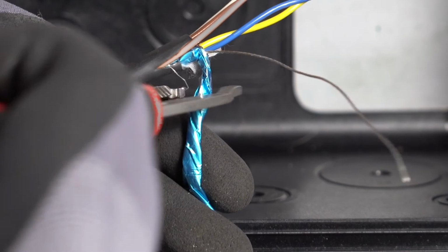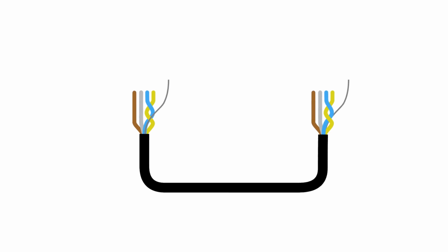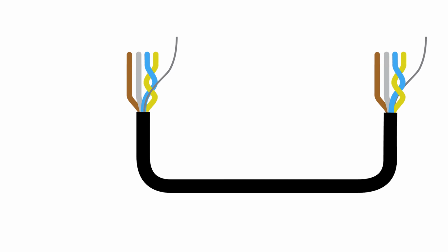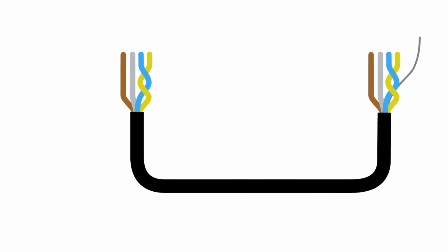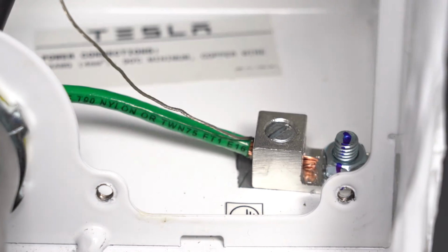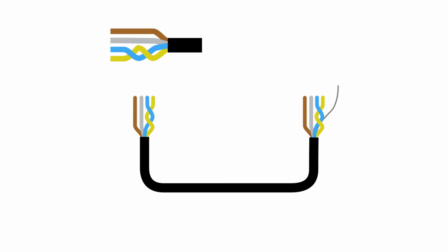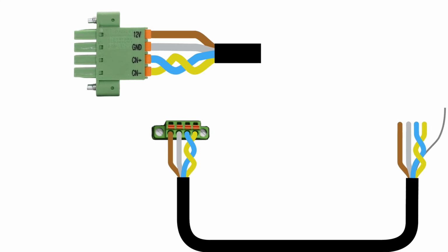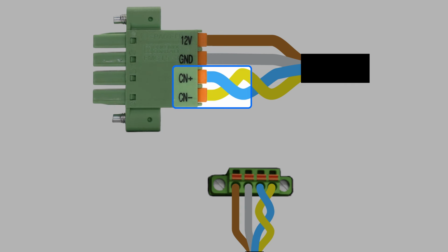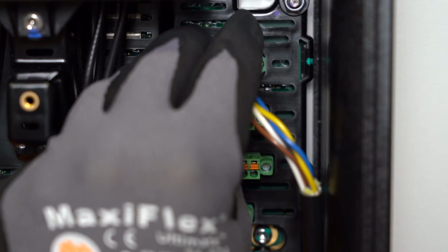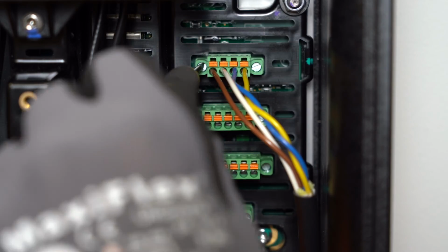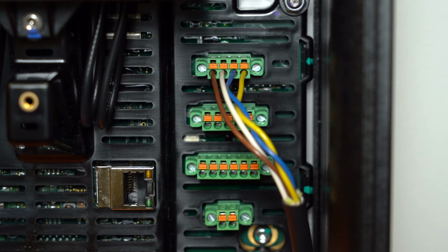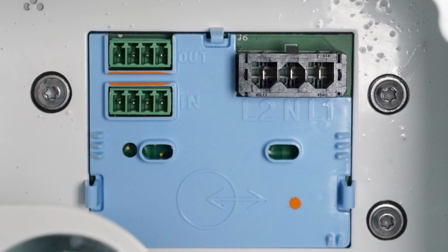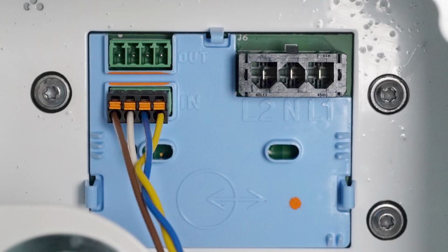Remove the outer jacket from the 4-conductor communication cable. On the Backup Gateway side of the cable, cut back the drain wire. On the Powerwall side, the drain wire will be terminated at the earth lug, along with the grounding conductor. Strip and insert the wires into the 4-pin connector in the Backup Gateway. Ensure that the twisted pair is used for CAN high and CAN low connections. Plug the green connector into the port inside of Backup Gateway and secure the 2 set screws on each side. The other end of this cable is connected inside of Powerwall, which is covered in the Powerwall wiring video.